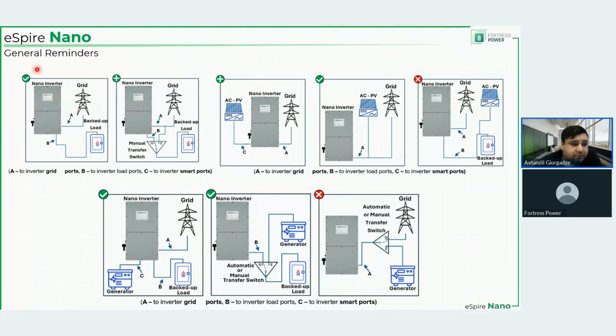So just a small note on the designation before we move on. This check mark here shows this is an acceptable good solution, plus shows it's a preferred solution, and the red X or tilted cross or whatever you want to call it shows that no, this is a no-go, you cannot have it. Now, preferred solution: you have AC coupled PV connecting through the nano inverter to the smart ports, grid connecting to the grid ports, then the backed up load will connect to the backed up load ports, and the battery will connect to the battery ports.